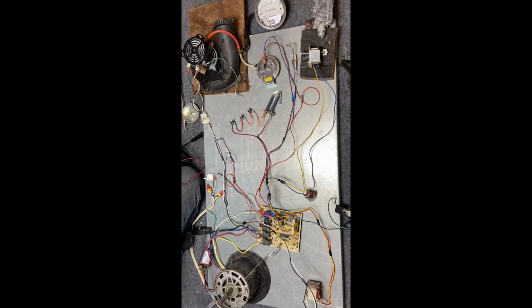So the only way we're going to check speeds is we're going to use the amperage of this. So that's how this multi-speed motor works. The capacitor, we'll check that a little bit later. We're going to disconnect all the voltage and discharge that capacitor before we check it.